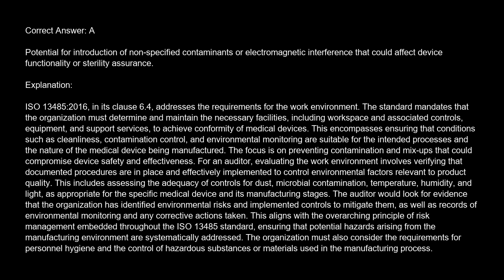For an auditor, evaluating the work environment involves verifying that documented procedures are in place and effectively implemented to control environmental factors relevant to product quality. This includes assessing the adequacy of controls for dust, microbial contamination, temperature, humidity, and light, as appropriate for the specific medical device and its manufacturing stages.